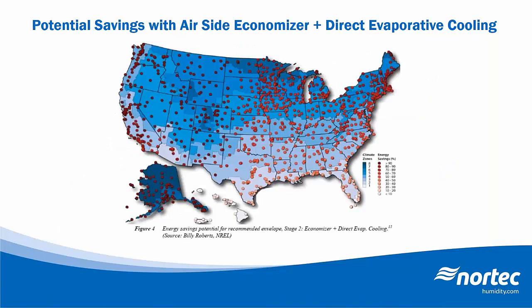So if we go back and look at the map from the NREL, with an airside economizer plus the addition of a direct evaporative cooling system, we can see that it significantly increases the average potential energy savings to around 80-90% over, say, a traditional DX cooling system. Now, certainly the potential energy savings through economization and evaporative assist will depend on your specific climate region and will need to be evaluated for the location of that data center. The Green Grid actually has a great web-based calculator that you can use to help run estimated cost savings for different locations based on your zip code.